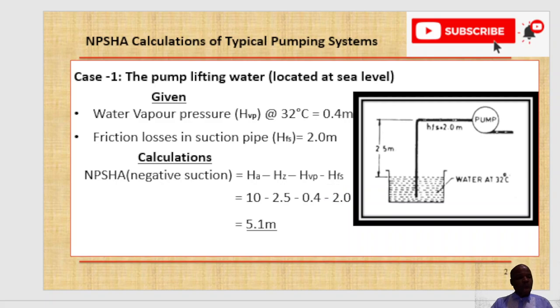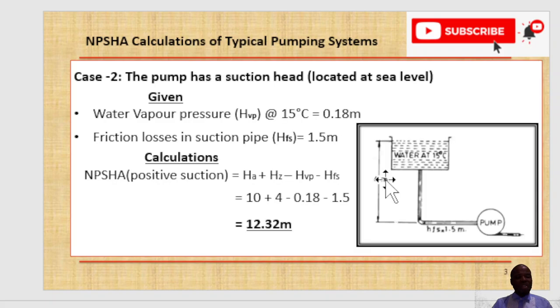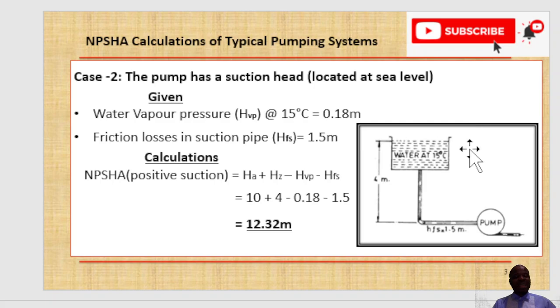Now we look at Case 2. In this case your suction tank is located above the pump centerline. When you have this configuration, the pump has a suction head — it is a positive suction system. How you obtain NPSHA for this kind of system is different from Case 1, where the suction tank is located below the pump centerline.